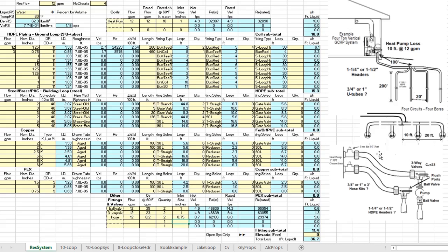You look at where this goes in, there's an HDPE T right there. Okay, so it's a 1 inch, I think. So we're going to put 12 right here, GPM, and we don't have any runs. All we have here is a T, but T run, so we have 2 of those. And I think one other thing I missed was the run of T here, so I'm going to put that in on the U-tube. I missed that earlier, so let's find that. Butt tee run, okay, and there's 2 of those, so it's not going to make much difference, but we got everything in. I'm pretty sure we do.